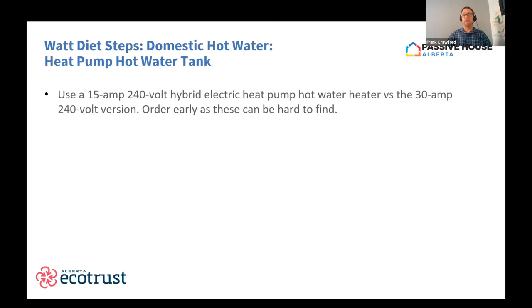Finally, we're probably going to want to electrify our domestic hot water, as lots of us have natural gas hot water tanks. So here we're going to most likely use what is called a heat pump hot water tank, or sometimes called a hybrid electric heat pump hot water tank. And the biggest trick here is when we're buying that piece of equipment, we want to use one that is 15 amps, 240 volts, as opposed to 30 amps, 240 volts. They are a little harder to find, so order early.